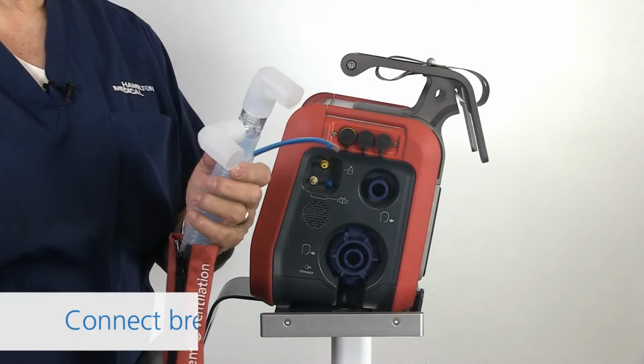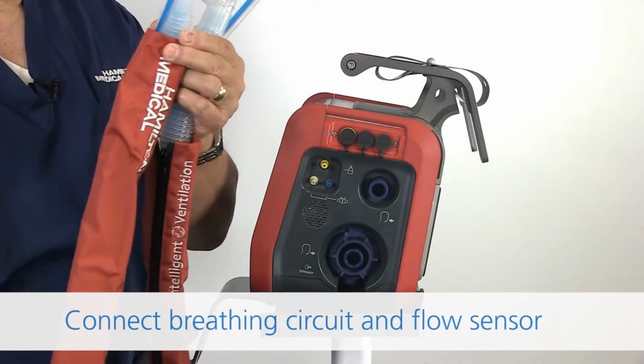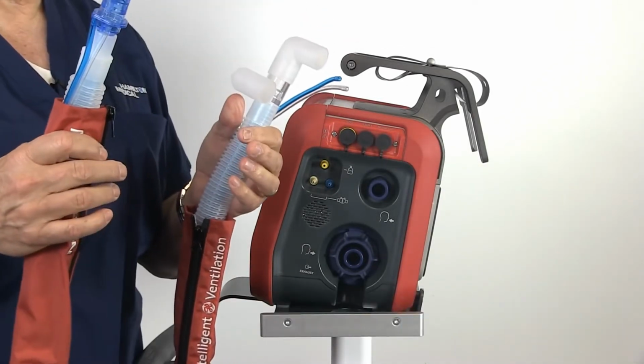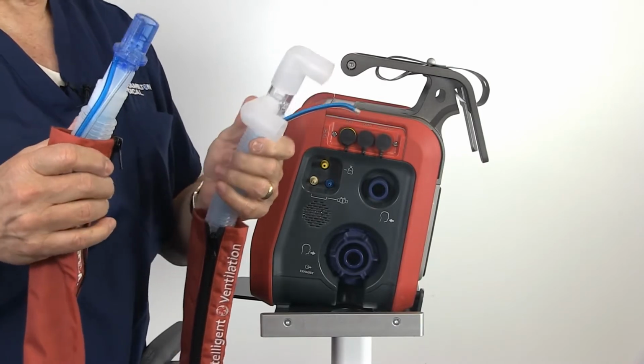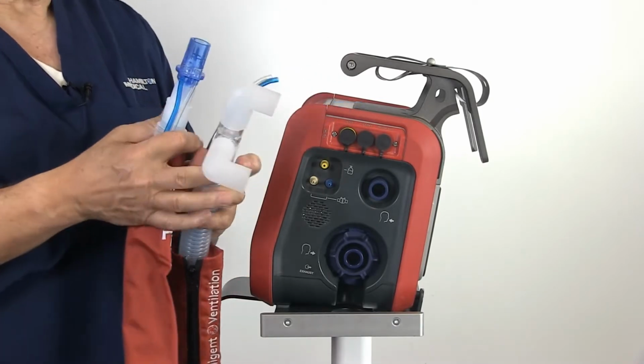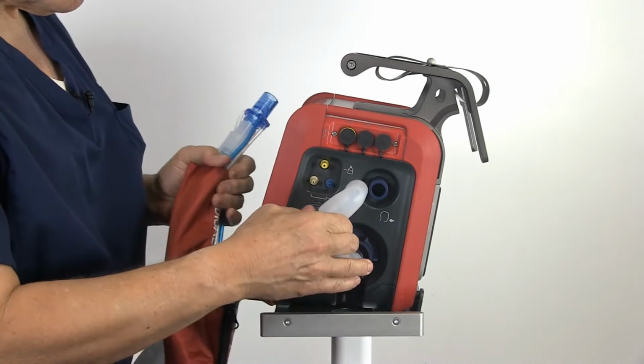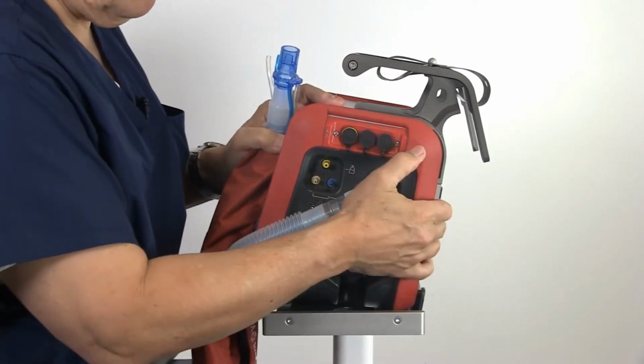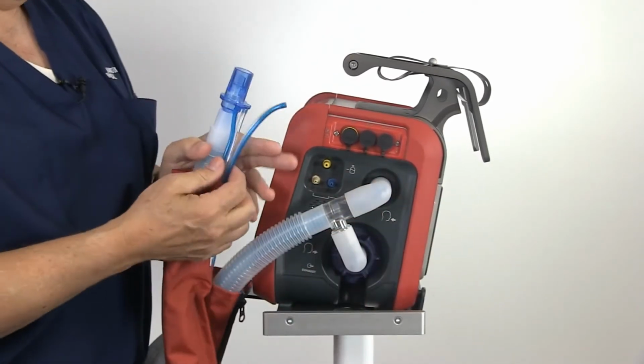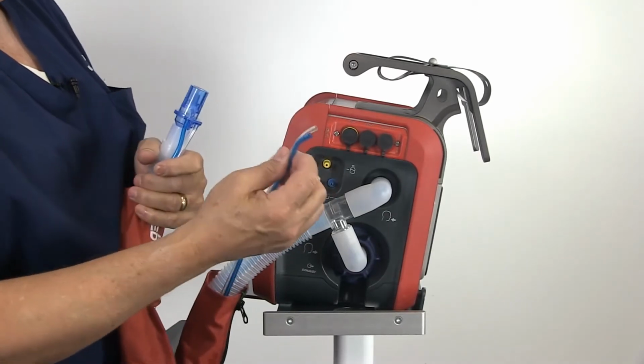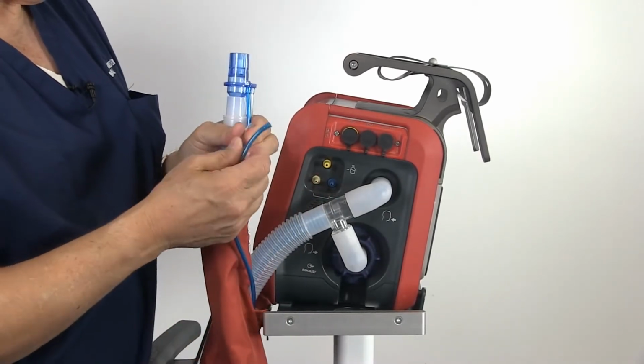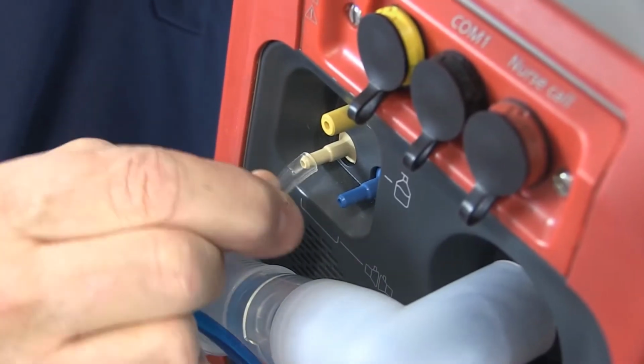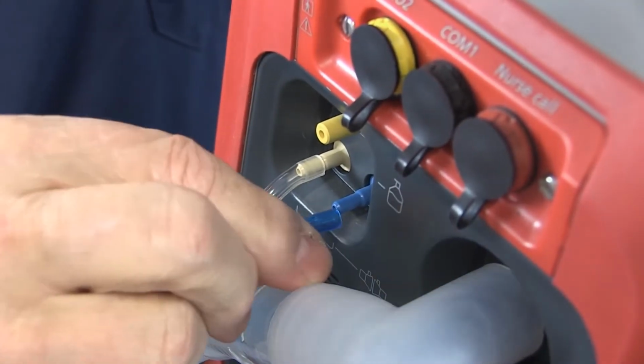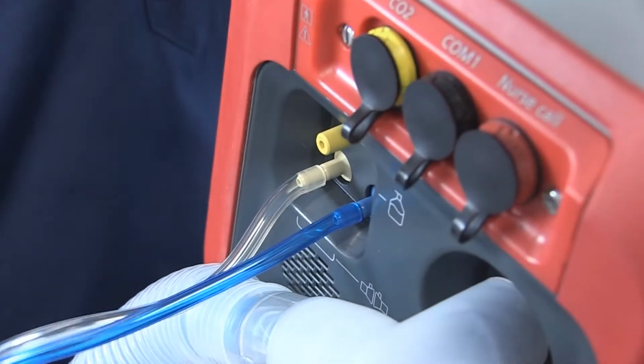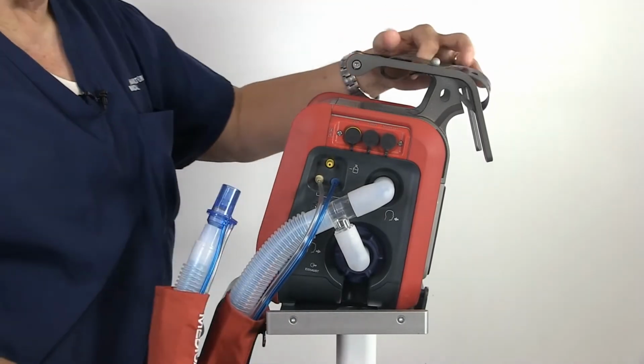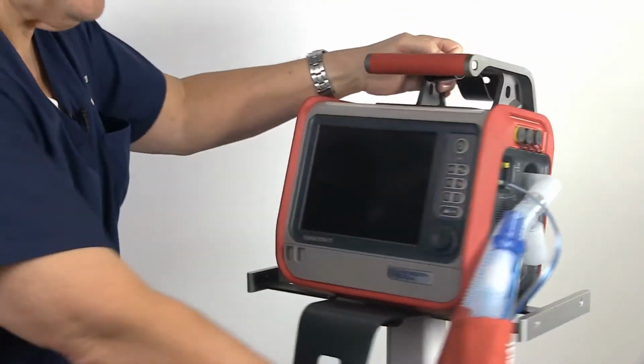So now we have the circuit, and as you'll notice, we'll have a sleeve on the circuit. This keeps everything uniform and keeps the lines from getting tangled. To put the circuit on, it'll only fit in one direction, and it's designed that way on purpose so we can't get mixed up. Then you've got what we call your flow sensor lines. You've got the white hookup and the blue hookup. They're color coded, so you cannot mess them up. That's the circuit. Now we're all set to go.